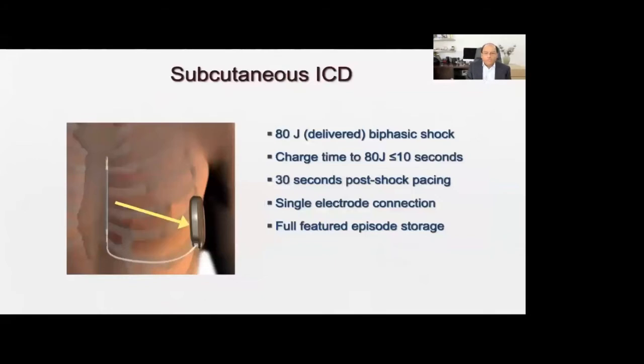The device delivers an 80 joule fixed non-programmable biphasic shock. The charge time is about 10 seconds or less, and there is 30-second post-shock pacing, which is basically high energy pacing through the chest wall. And of course, there is full-featured episode storage.